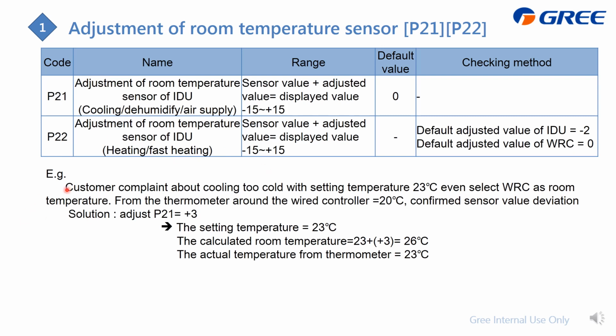And here is an example where the customer complained about the cooling being too cold with the setting temperature at 23. Even though we selected the wire controller as the room temperature sensor, the thermometer around the wire controller detected 20 degrees, so we confirmed this is due to sensor value deviation. Our solution is to adjust P21, which is for cooling, to +3. Then the setting temperature is still 23, but the calculation for this indoor unit has changed to 26 degrees. So the final result, for the calculation of the GMV system, is 23, which can meet the customer's requirement.